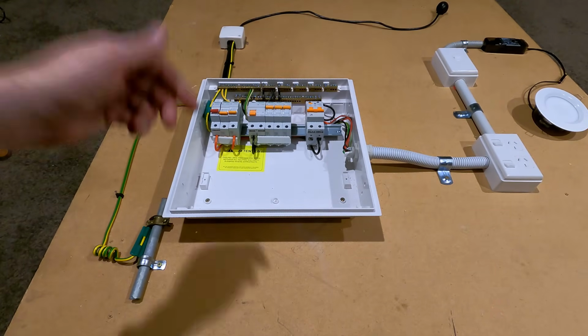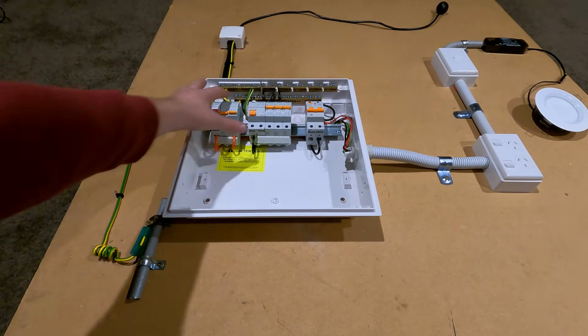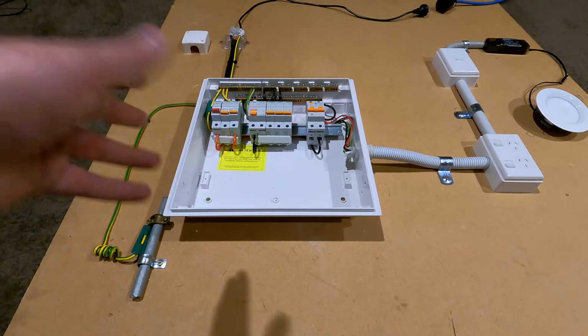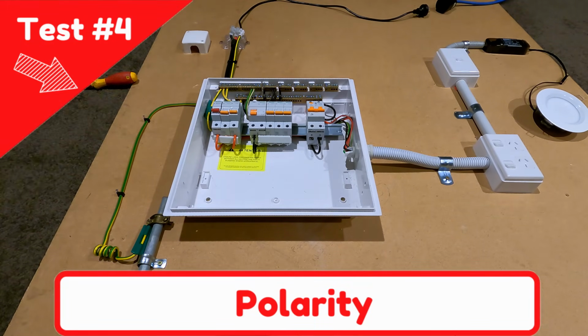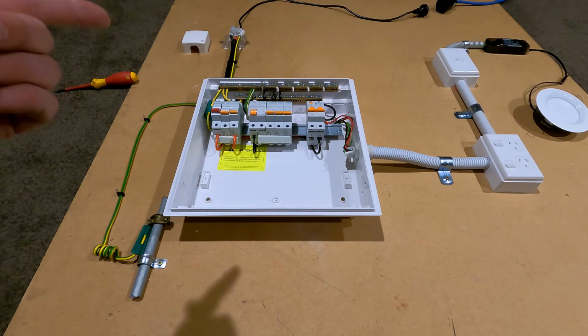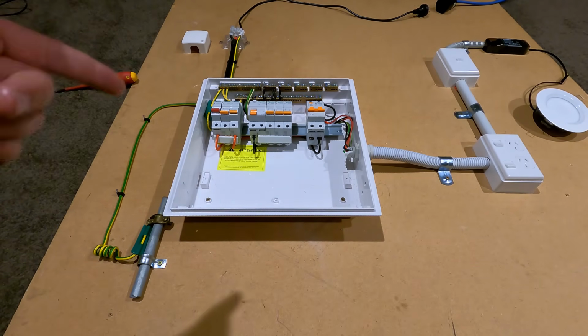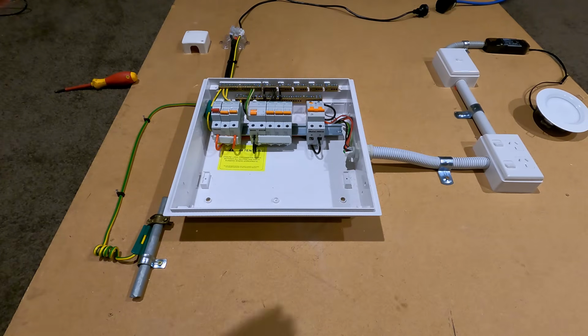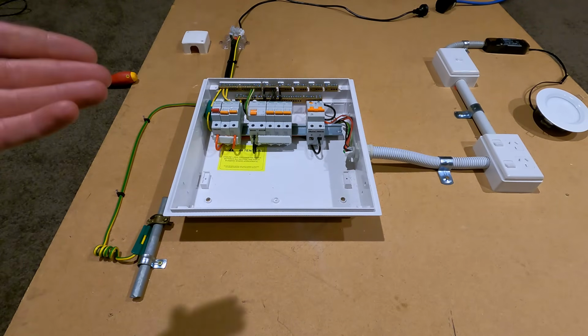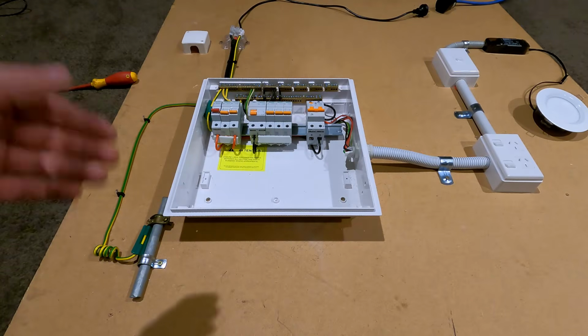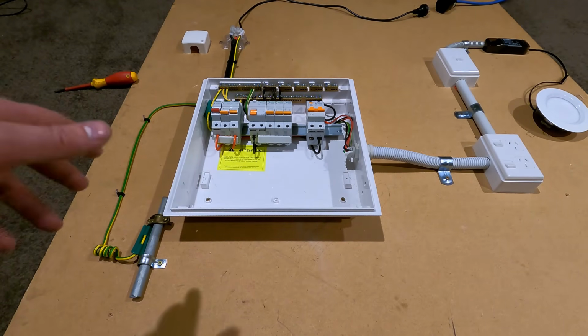Once you're done, throw your MEN link back in as well. And the next tests we're going to run through are polarity tests. Now the first one we're going to do is on the line side mains. So from the meter box mains to the main switch here, we're just going to ensure that we've got the right polarities on the cables. Even though you can visually see it, it is a mandatory test to go through.